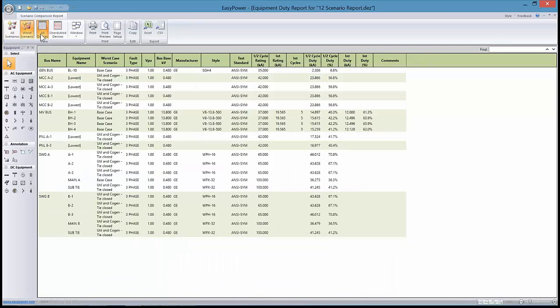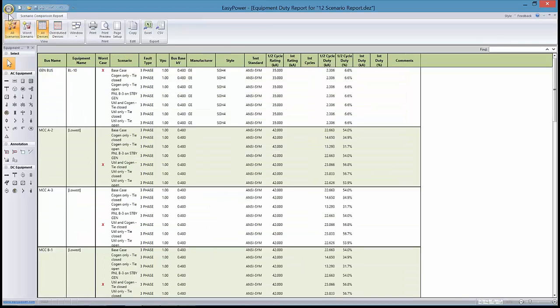And as I mentioned before, we can produce equipment duty and look at essentially the most restrictive headroom and decide whether or not we need to make adjustments for our system duty-wise. It may be that we could be over-dutied in situations that are not that frequently run.